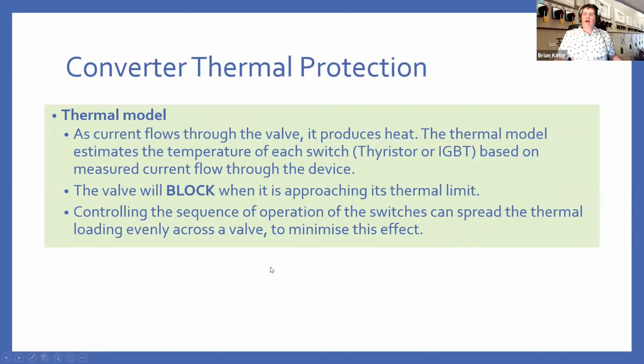Thermal models are also used because as the current flows through each valve, it produces heat, and what you don't want is for the switching device to overheat and burn out. So each device will have its own thermal model running, and it will block if you're approaching thermal limit to prevent you from using it. And this prevents the spread of thermal cascades across your valve. The details of this are usually bespoke to the manufacturer, but there are some standards, and people like CIGRE and IEEE have published thermal modeling standards that you can look at.